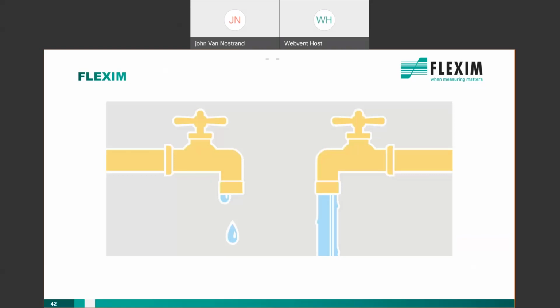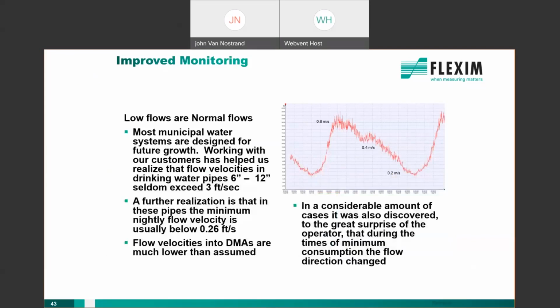Turn down is also a major one. Turn down refers to the operational range of a device versus what the meter is capable of measuring between the low range and the high range. So just to give you an idea, we assist a lot of water utilities, and what we've learned is that most drinking water piping systems flow below 3 feet per second, even during peak demand. So off-peak times, the flow can diminish to velocities below 0.26 feet per second. Sometimes it even flows backwards. I've seen that before too.